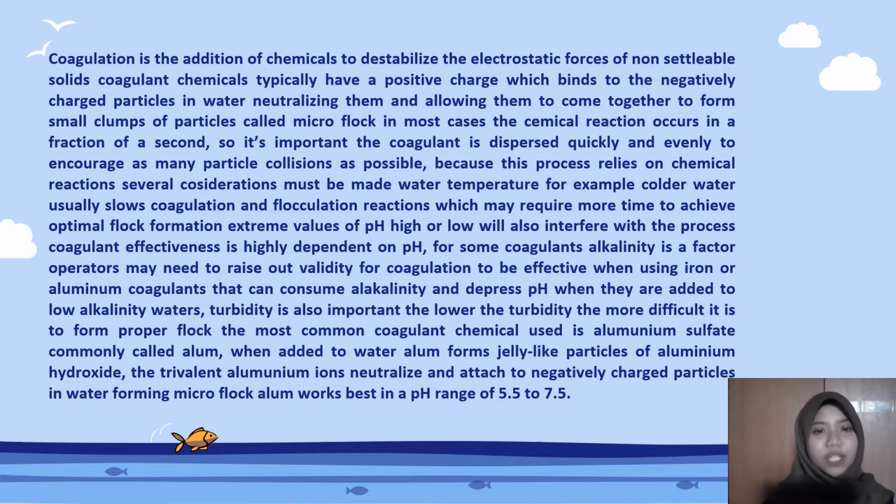Coagulation is the addition of chemicals to destabilize the electrostatic forces of non settleable solids. Coagulant chemicals typically have a positive charge, which binds to the negatively charged particles in water, neutralizing them and allowing them to come together to form small clumps of particles called microfloc.